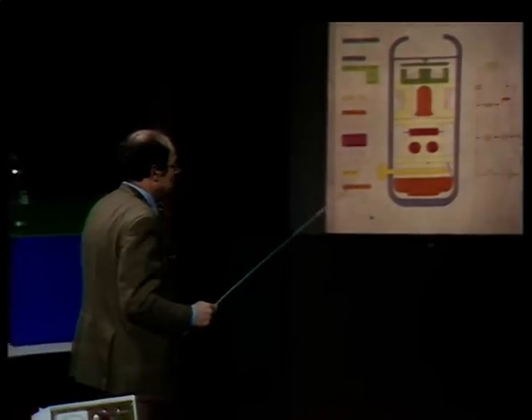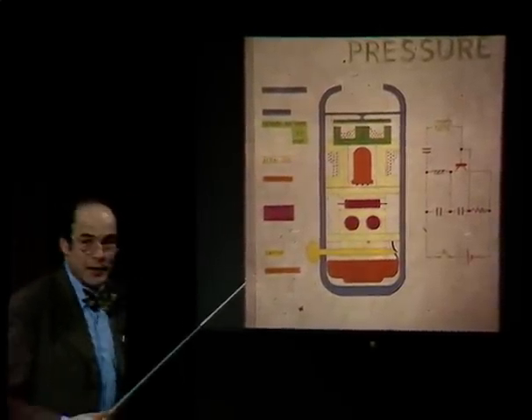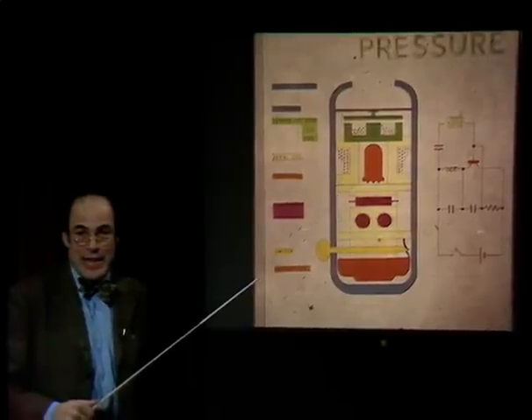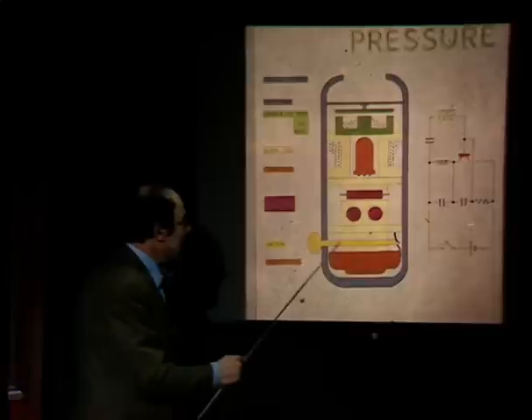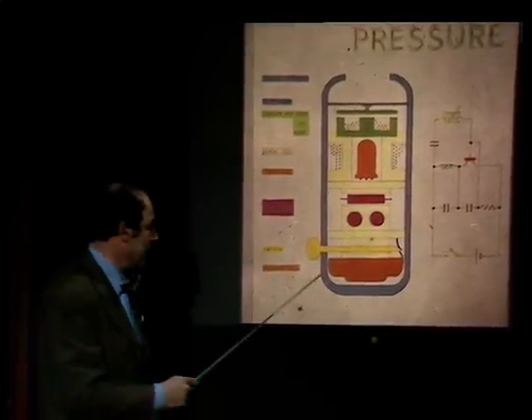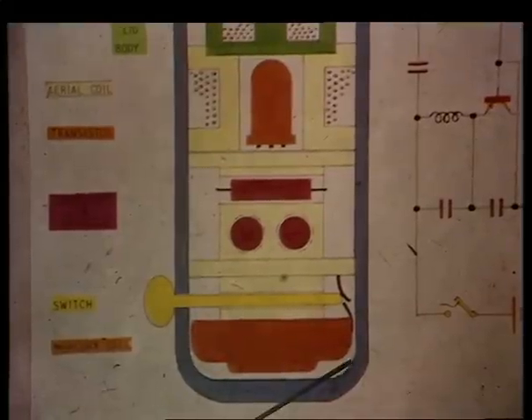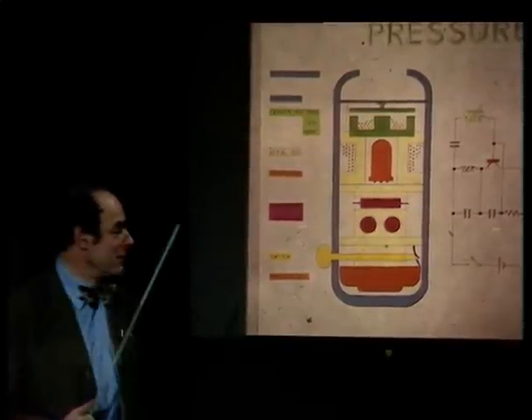Well, here's a rather formalized cross-section of a radio pill, or rather more elaborately, an endoradiosonde, as they are sometimes known. It consists really of three quite separate compartments. The first part at the bottom here is a battery which powers it, and depending on the exact construction, these batteries will last anything from about 24 hours to perhaps 3 or 4 days. There isn't much point in making them last very much longer than that, for reasons which I think will be obvious to all of you.